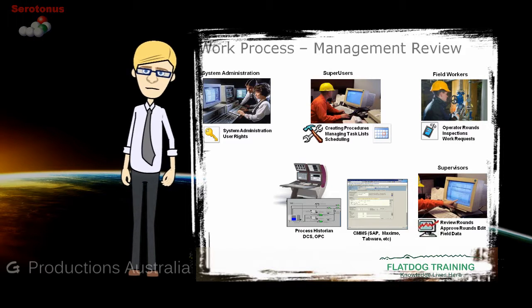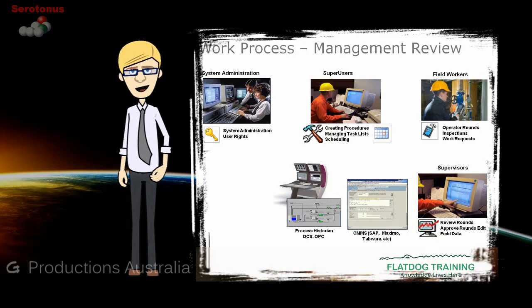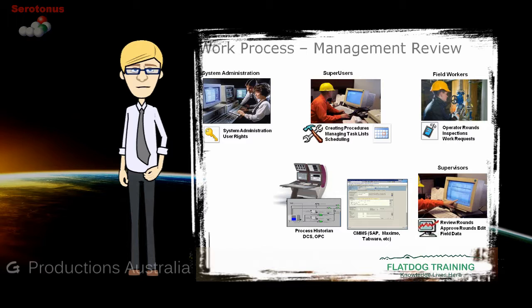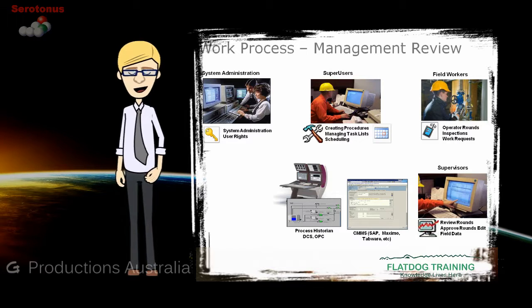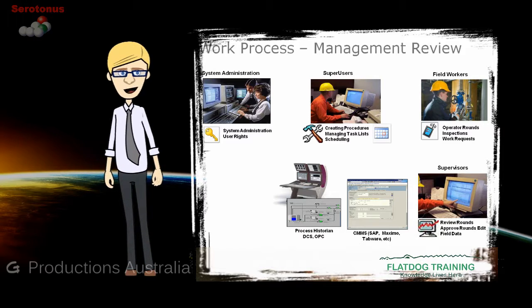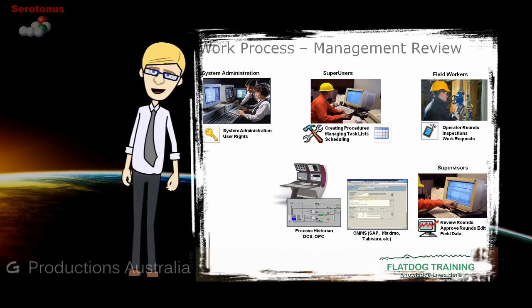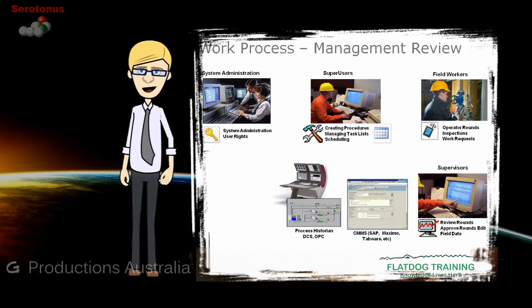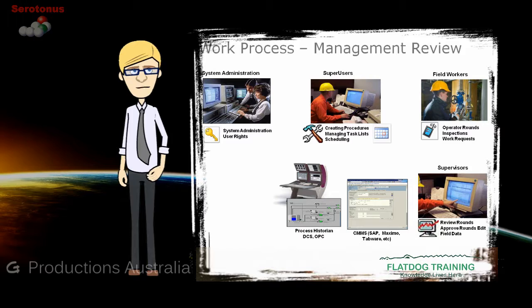Then the field workers log into the handheld, get their procedure for the day, and walk out and go about doing their rounds. Now, whenever they go out to the system, they can either scan a barcode on an asset or pick up the data from an asset tag called an RFID tag. An RFID tag can hold the asset name and number, and when you scan that, Intelatrac can bring up the particular procedure for that asset immediately. The operator doesn't even have to scroll through all his procedures to see which one is particular for that asset. He just scans the RFID tag or barcode, and it takes him right to that particular procedure that he needs to perform for that day.